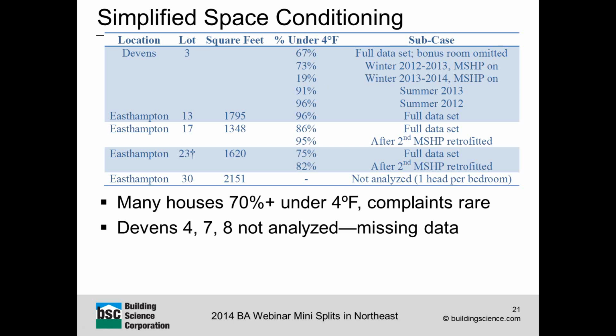One interesting thing was that we looked at both the wintertime season performance as well as the summertime season performance. What we saw was that in the summer, the temperature variation was actually a little less than in the winter. The reason for this is that the temperature difference between indoor and outdoor is a lot lower in summertime design conditions versus wintertime design conditions. Just think about it, New England in the winter, 70 degrees versus 0 degrees, about a 70-degree delta T. Summertime, 70 degrees versus 85, 90 degrees, a 20-degree delta T.